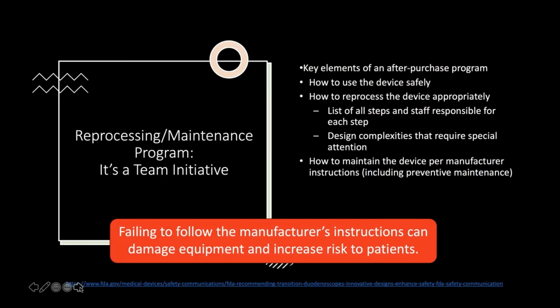So let's talk for a second about maintenance. This is a big area: if you look at the MAUDE database that FDA uses to track adverse events, you'll find a lot of clarity in there about the known risk associated with lack of proper maintenance, especially around ERCPs. There has been a big push over the last few years to have a scheduled set of maintenance for reusable duodenoscopes, for good reason, right? Because previously there was no maintenance schedule that said you need to send it in every 6 months or a year, here are the things to look for for wear and tear. None of that really existed. And so that prevented us from knowingly being able to use that device safely, right?